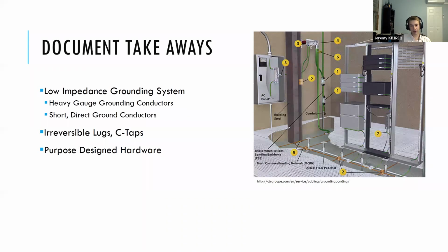The other piece is purpose designed hardware. And well, if we're not going to be audited on these standards, or we're not going to hyper focus on meeting the letter of the standard, a UL stamp may not get us anything. But it's the idea that you use things as they're intended, especially when it comes to devices that are making these ground connections. You want something that is designed to conduct electricity. It's designed to conduct a lot of electricity. If it's going to be outside, it's designed to be outside in the elements. Or if precautions have to be taken in the installation, if certain steps have to be followed, that those are followed.